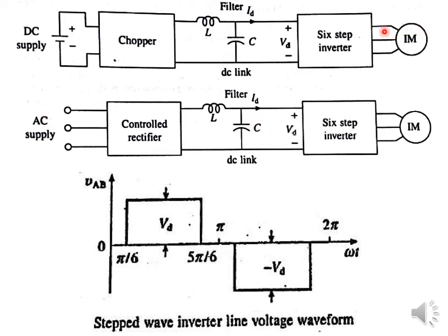In both cases, we get a variable voltage variable frequency supply at the induction motor terminals. This figure shows the line voltage at the induction motor terminals. One of the line voltages, VAB, is shown. The waveform of VAB is a stepped waveform, which will obviously contain a large amount of harmonics. The peak value or magnitude of the line voltage is equal to VD, which is the input DC voltage.